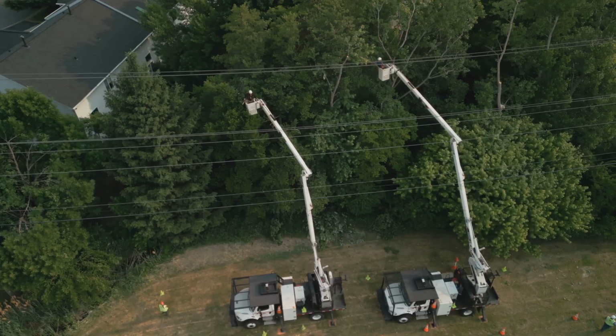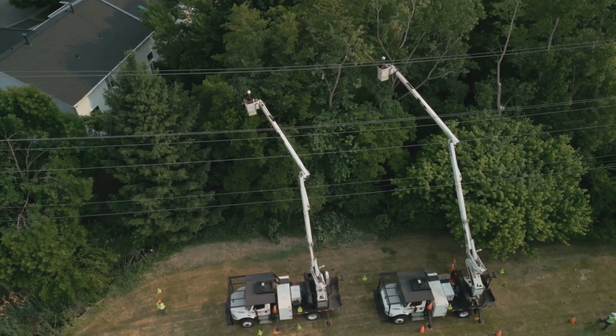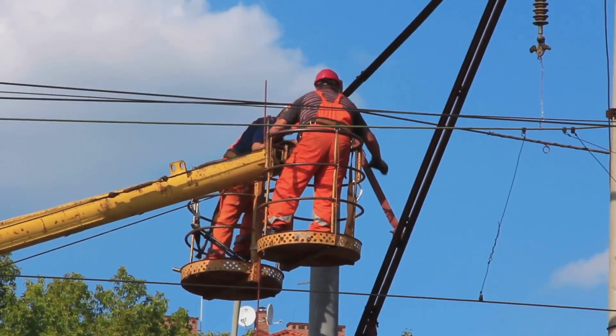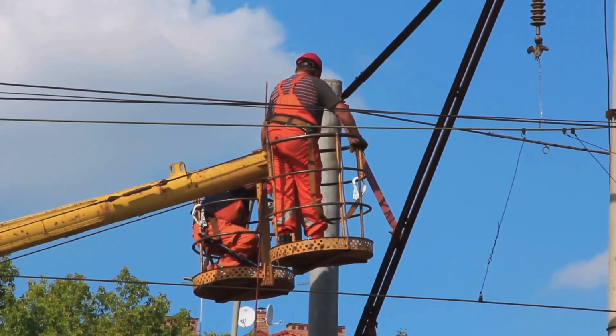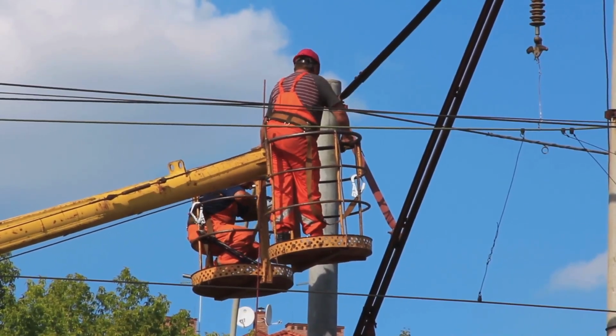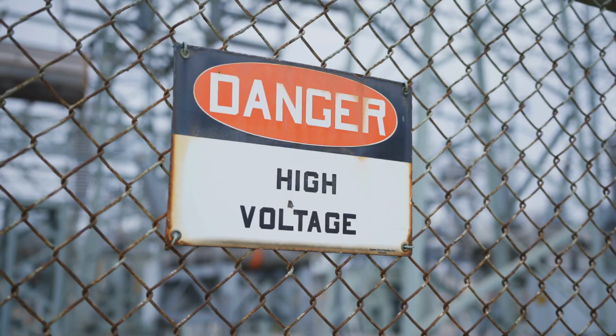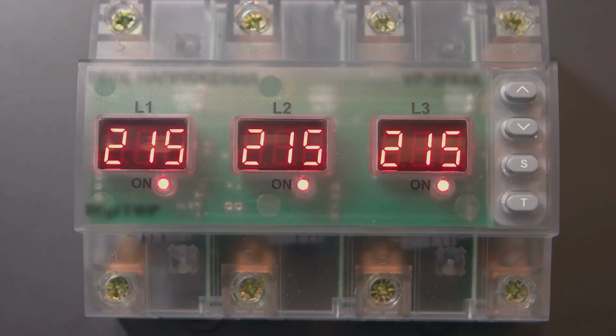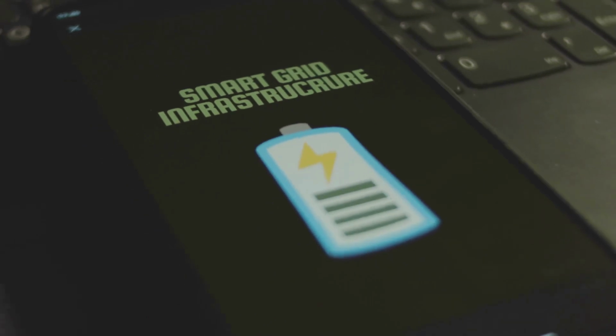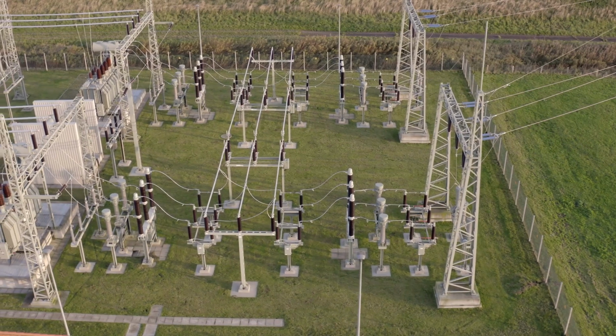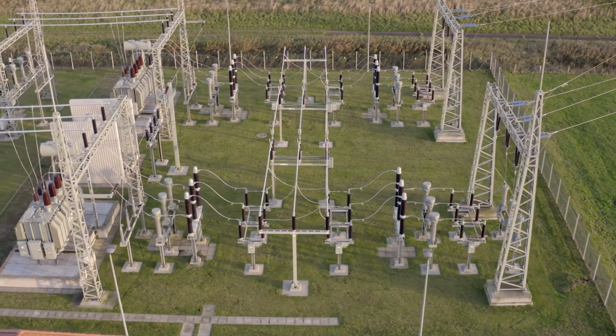Clause 4.4, Prevention of Unintentional Energization. One of the most critical risks during restoration from faults is a DER backfeeding a de-energized grid. This can endanger line workers and damage equipment. DERs must monitor line voltage and confirm the grid is alive before reconnecting. This clause ensures that DERs only re-energize when grid conditions are clearly stable, helping transition safely from FRT to normal operation.